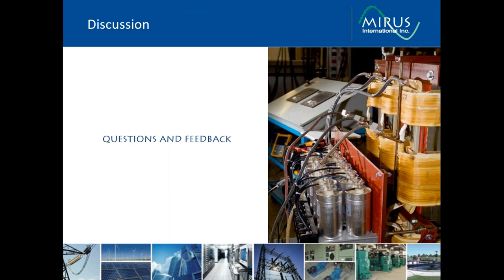Okay, the next question, we have a couple of questions relating to sizing of Lineators on multiple loads. They're both kind of getting to the question of, if you have an application where you have multiple drives, can you feed them from one single Lineator or wide spectrum harmonic filter? Yeah, absolutely. Basically, if you have multiple drives, you have to determine what your maximum load will be when operating those multiple drives, and then just size the input filter to that maximum loading. We have many applications where that is done.